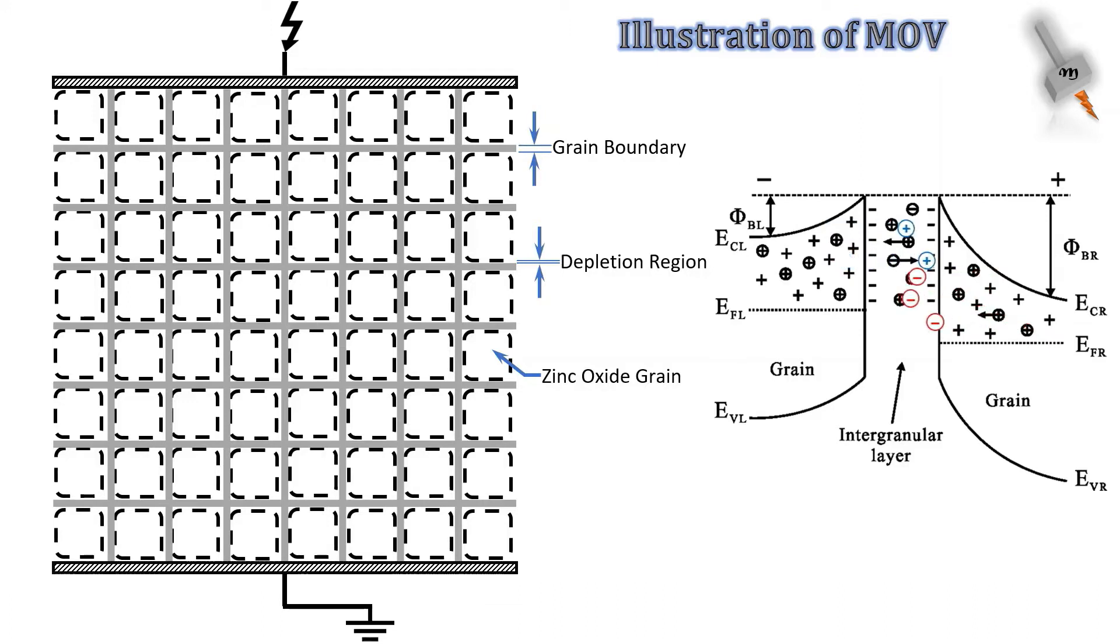At this point, the current increases from the range of microamps to milliamps. A point comes when the applied voltage increases to an extent that the grain boundary breaks down and there is a rapid increase in current. At that point, the current flows from a few amperes to few hundred or few kiloamps.